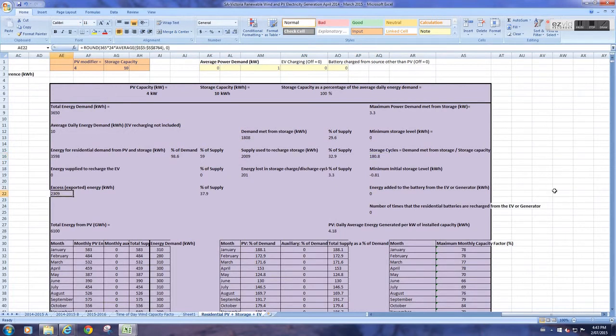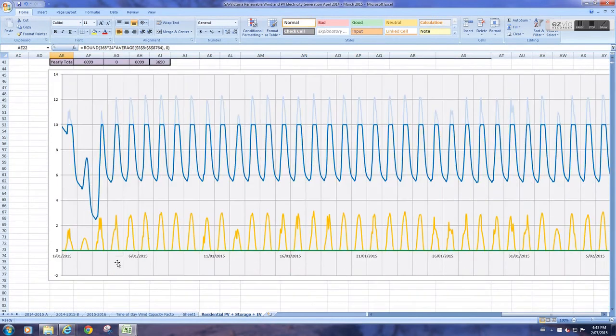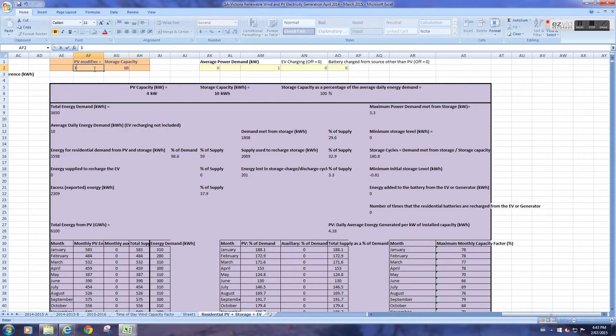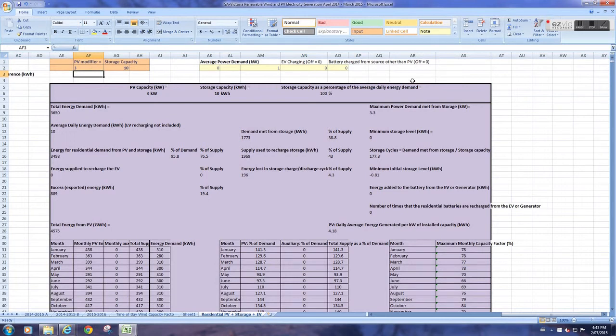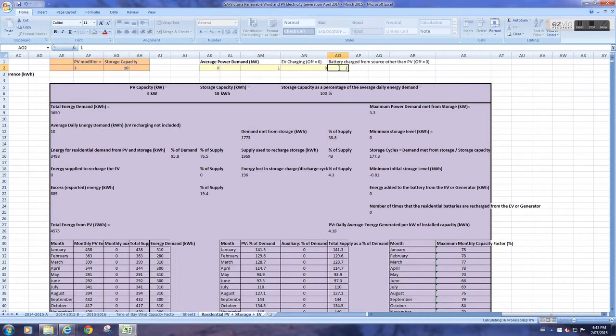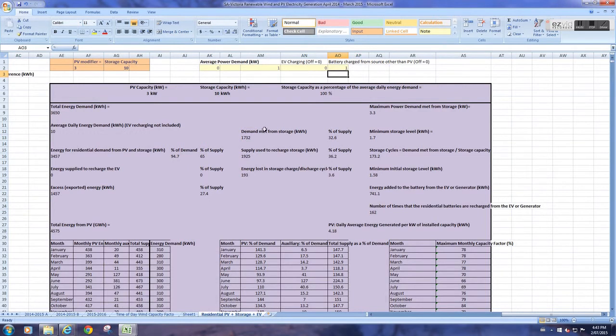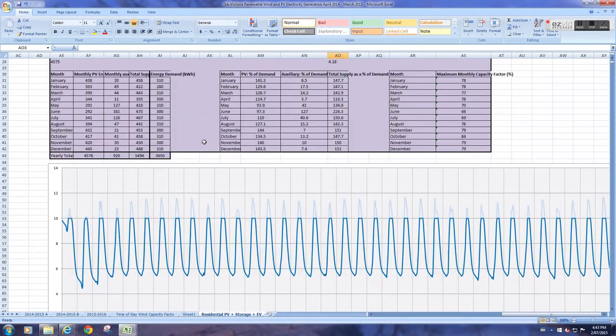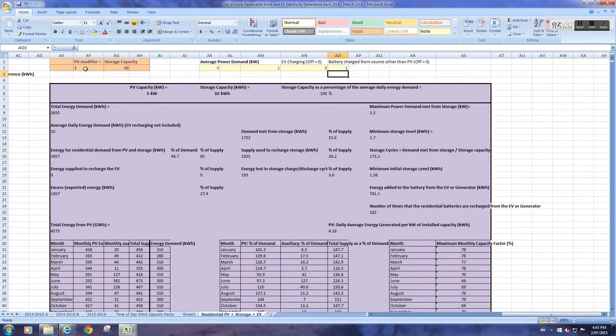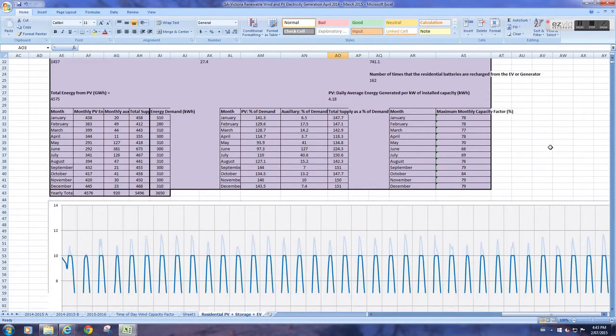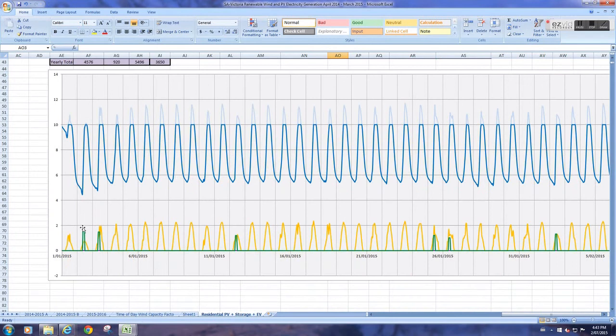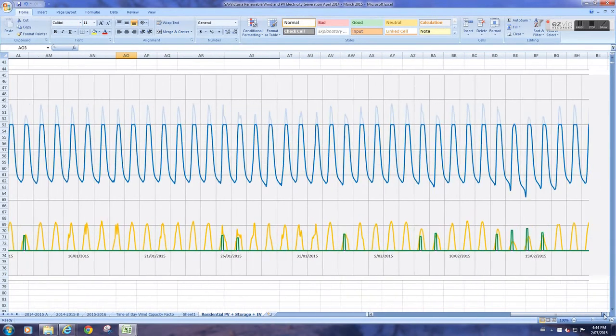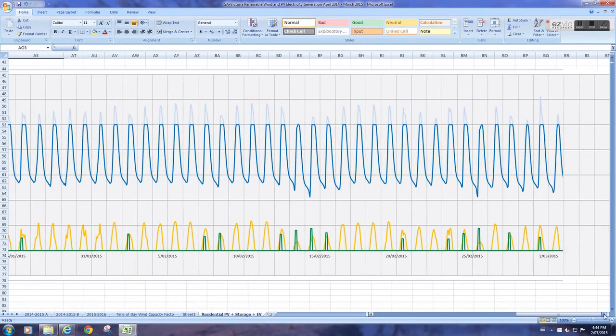Now, that's for an on-grid system where you're still connected to the electricity in the main power supply. You're exporting your excess, and when you run out of battery power and PV, wherever it might be, you are still getting electricity from the grid. What happens if you go off-grid? Now, the spreadsheet can model that as well. If you go off-grid, you'll need a diesel generator as backup. So, what I'm going to do here, I'm going to put a number in here. Anything other than zero will do. And what I've done is turn on a backup generator. So, now what the model is showing that during the year, I've got the 3 kilowatts of PV panels on my roof, I've got 10 kilowatt-hours of storage, I now have a diesel generator to use when the battery runs out. And what the model shows is all the times that I'd be using the generator and how much energy I'd have to receive from the generator.